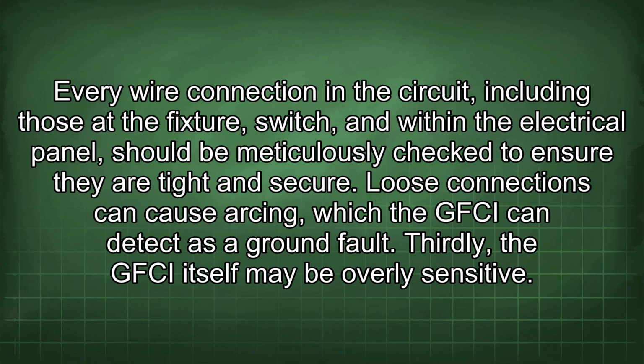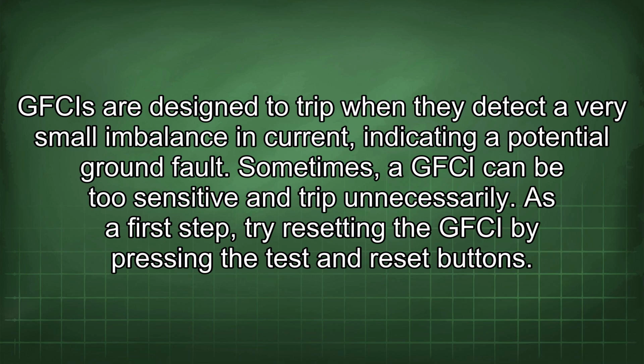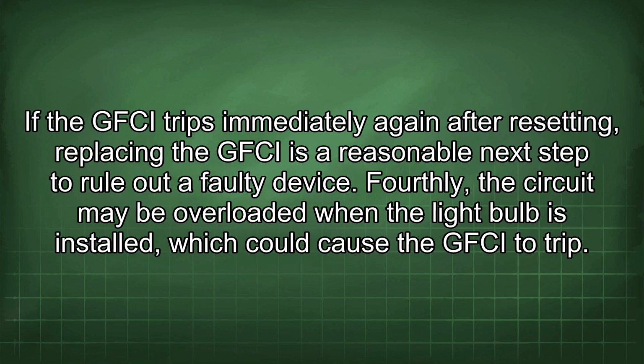Thirdly, the GFCI itself may be overly sensitive. GFCIs are designed to trip when they detect a very small imbalance in current, indicating a potential ground fault. Sometimes a GFCI can be too sensitive and trip unnecessarily. As a first step, try resetting the GFCI by pressing the test and reset buttons.